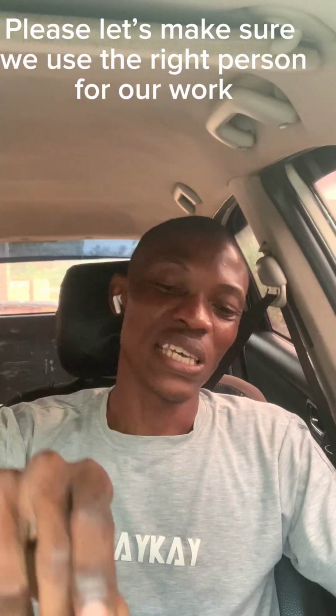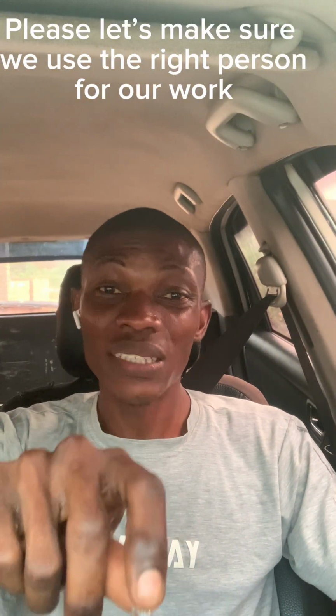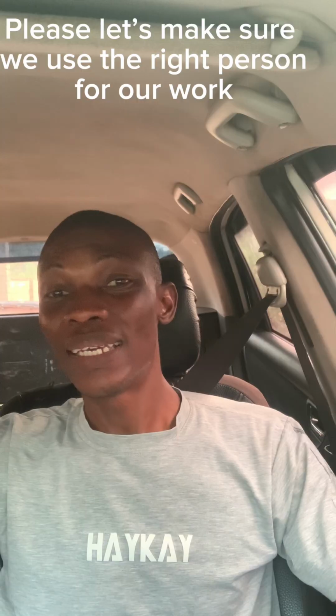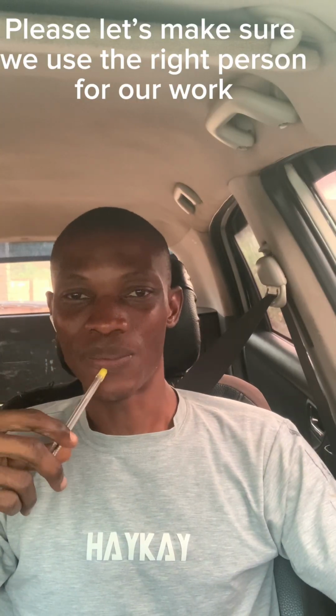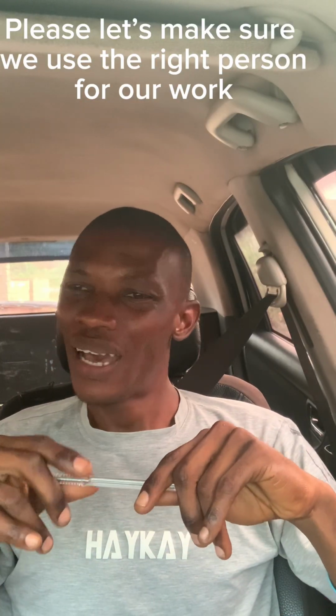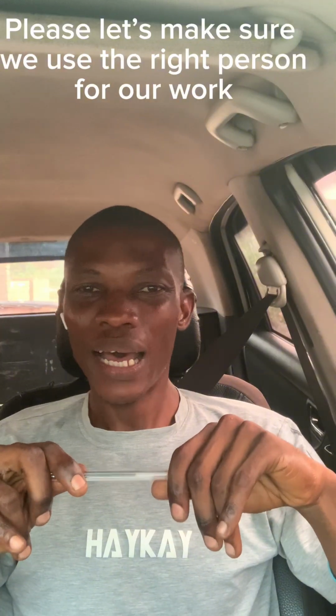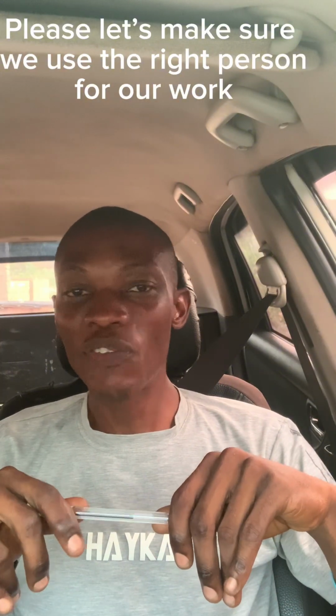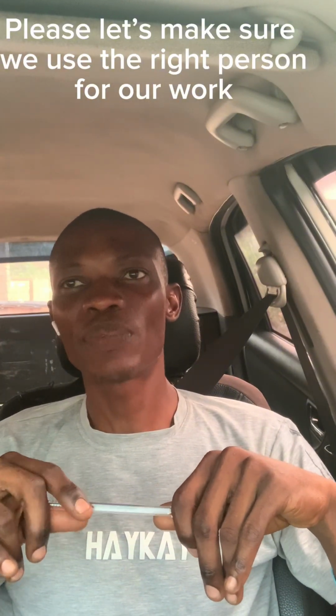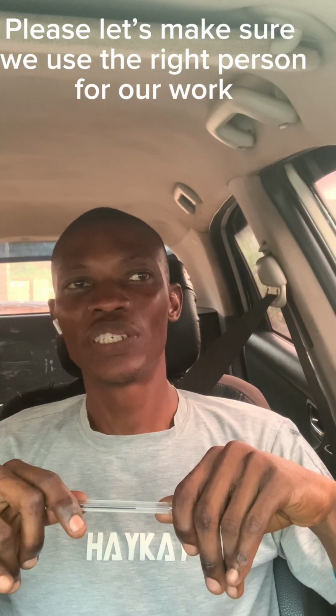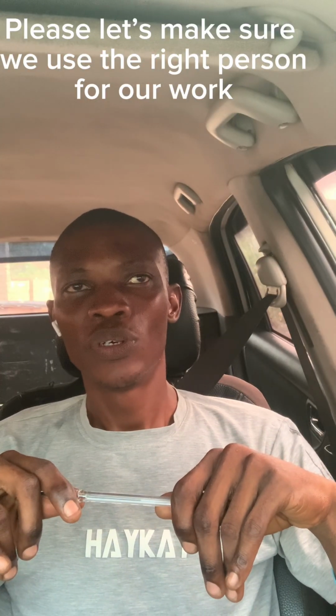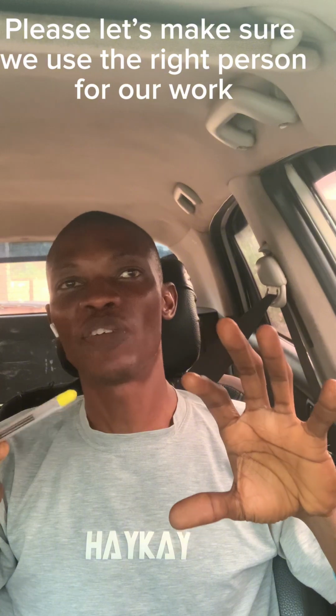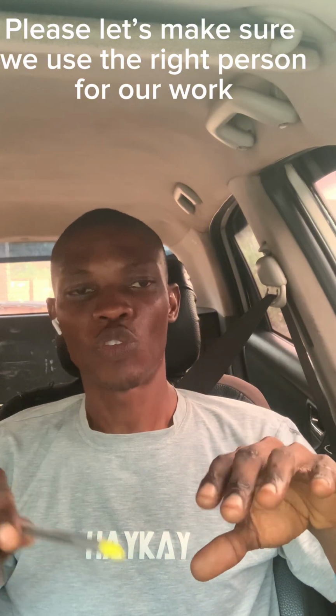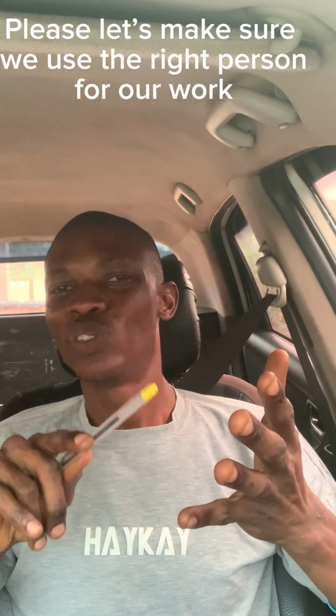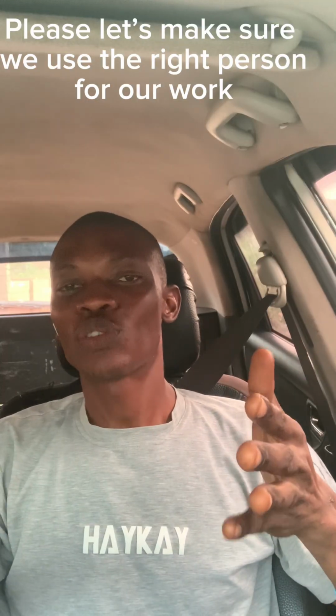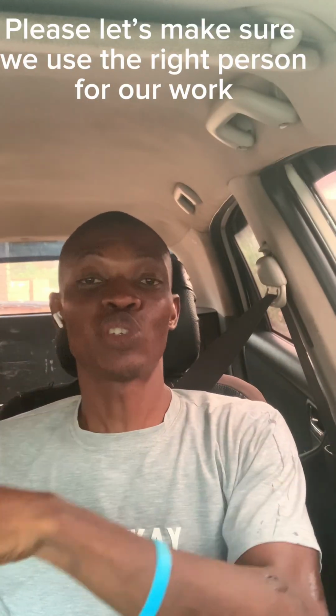How can you now use a 5,000 watts voltage regulator to power a 10 kVA inverter system? It can't even power it, because that system, while charging with grid, is going to draw a particular current that the manufacturer specified for it to draw from grid. That's one. Number two, it's going to bypass, so the load in your building is also going to be on it.